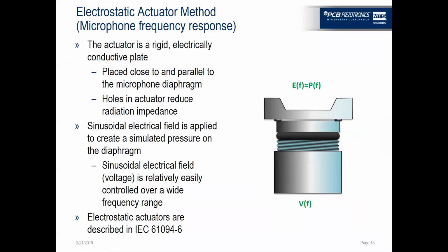From there, using known measurements from previously done testing, we will take that electrostatic actuator measurement and apply a correction to give you either the free field, random incident, or pressure response of your microphone. And even further from there, we can give you the responses with respect to a free field with a windscreen, various angles of incidence, various other adapters like nose cones.